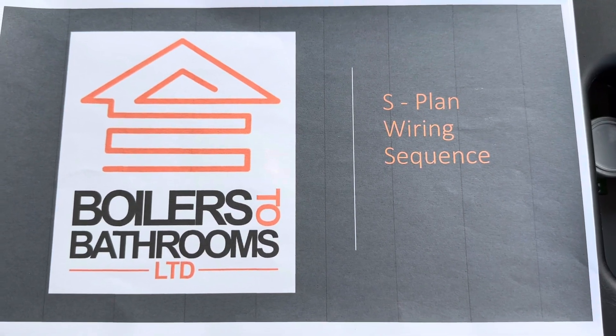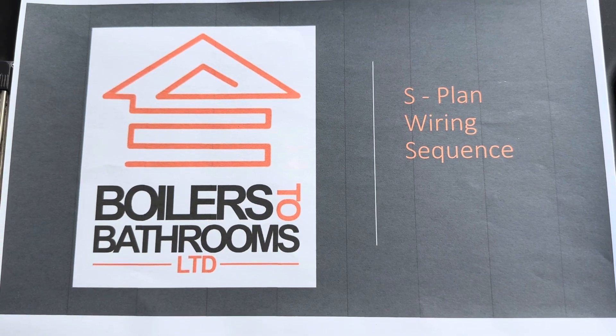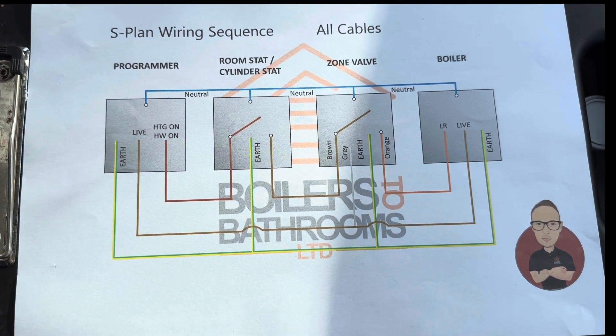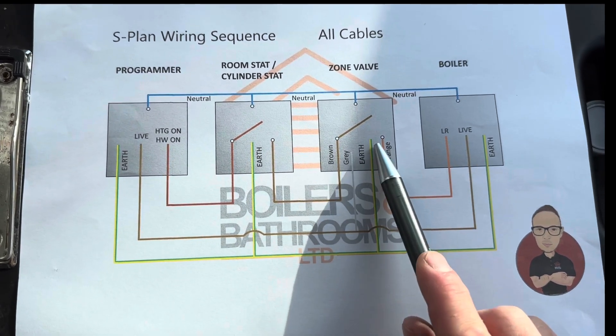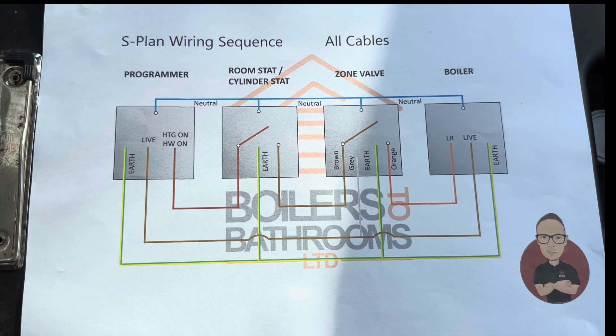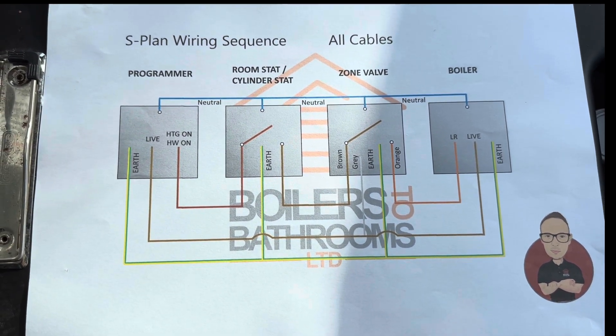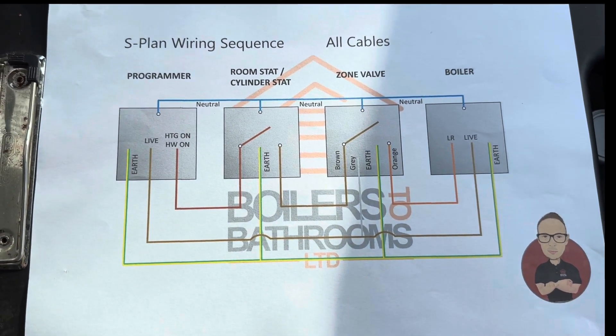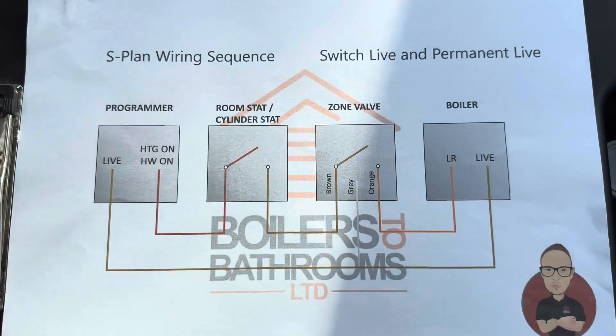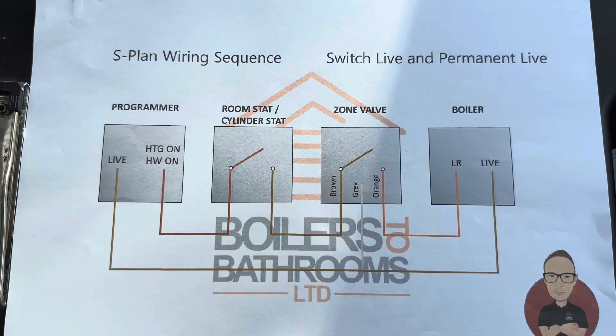We're going to go through the S-plan wiring sequence and fault finding in a bit more depth, with hopefully some easier diagrams to follow. In this diagram you've got all the cables: your earth, your neutrals, your lives, switch lives. On the zone valve we've got all five cables. I'll get rid of the earths and neutrals now to make it look a little bit easier to follow, so we've got our permanent lives.